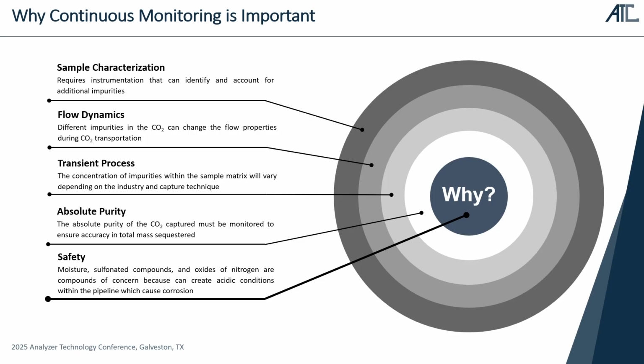We are required to monitor continuously because these processes are expected to be very transient. So in Europe, for example, you have multiple industries tying into one common pipeline. So you could have hydrogen production and then oil and gas production tying into the exact same pipeline. Upsets in process or shutdowns, stuff like that, could drastically change impurity levels that are present. The last two tie back to the absolute purity of CO2 that must be measured. We really need to characterize this entire sample to get an accurate idea of the flow dynamics within it. If we do not have an accurate flow measurement, we're not accurately measuring the total amount of CO2 that is sequestered.